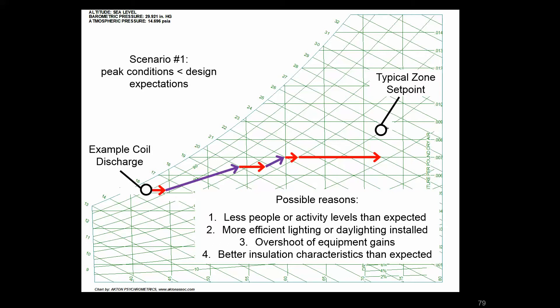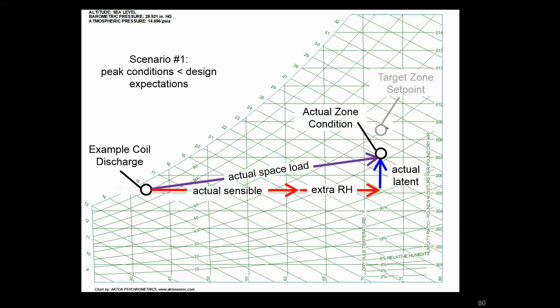Now we're going to look at what happens with some scenarios where loads are differing from their design, and that can happen for a few reasons. In this first scenario where we have peak conditions a little bit less than design expectations, that can be because the expectations weren't accurate, there was too much safety factor, or the assumptions made may have been valid but there's less load from people, from activities, from equipment like lighting or plug loads, or the building could just have better insulative qualities than was expected. But in any case, we have a scenario where we're having less loads and we're seeing quite a bit more reheat than we had before.